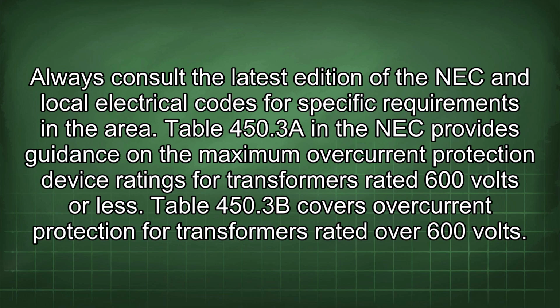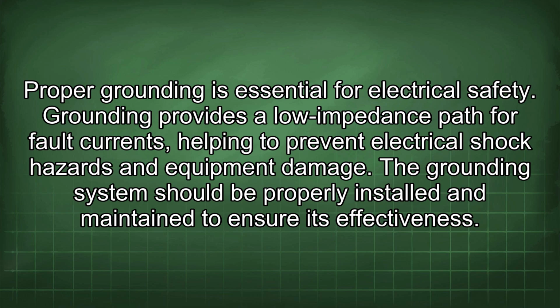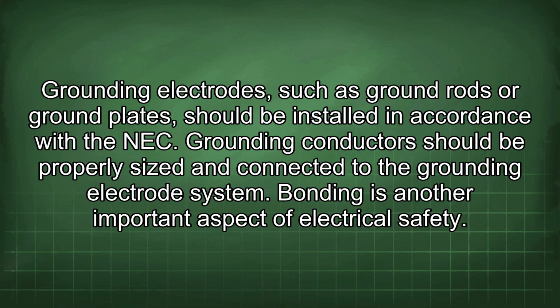Table 450.3(A) in the NEC provides guidance on the maximum overcurrent protection device ratings for transformers rated 600 volts or less. Table 450.3(B) covers overcurrent protection for transformers rated over 600 volts. Proper grounding is essential for electrical safety. Grounding provides a low impedance path for fault currents, helping to prevent electrical shock hazards and equipment damage. The grounding system should be properly installed and maintained to ensure its effectiveness. Grounding electrodes, such as ground rods or ground plates, should be installed in accordance with the NEC. Grounding conductors should be properly sized and connected to the grounding electrode system.